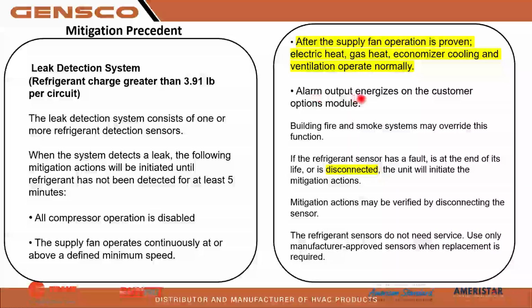So alarm output energizes on the customer options module. So we will have a customer options module if you need an alarm output tying into said building, and building fire and smoke systems may override this function. So you will need a customer options module if you have to tie into a building suppression system.